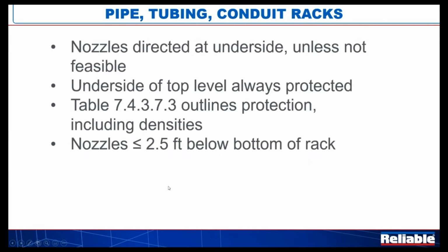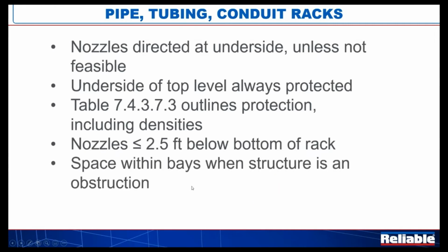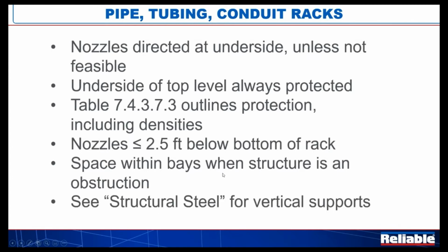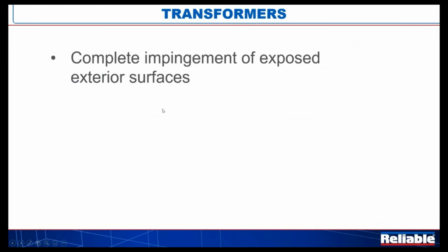And then finally, the nozzles at the underside, no more than 2.5 feet below the bottom of the rack. I did say finally, but there is one more, and it just kind of makes sense, right? If you're spraying at something and you're holding it up with a unistrut rack or whatever that is, that is an obstruction. What they would ask you to do is simply space within those stanchions or whatever they are, and you may need to protect them anyway. So again, space within the bays, and when you do that, obviously do it per the structural steel requirements.